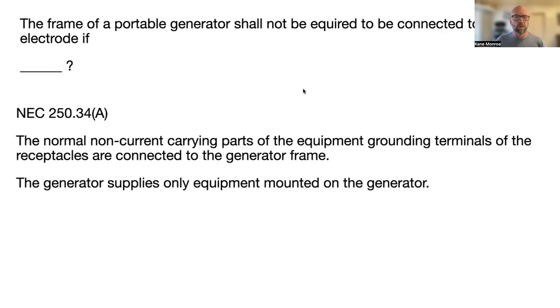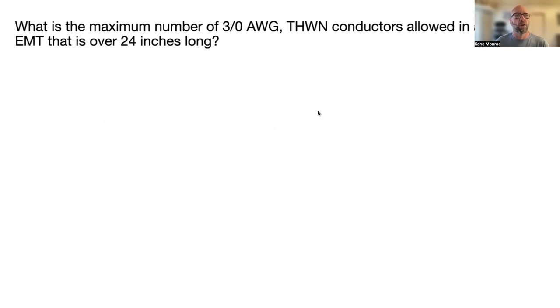Next question: a frame of a portable generator shall not be required to be connected to a grounding electrode if blank. Be careful — we're talking about grounding, which is covered under 250.34(A). The answer is: the non-current-carrying parts of the equipment and grounding terminals of the receptacles are connected to the generator frame, and the generator supplies only equipment mounted on the generator.